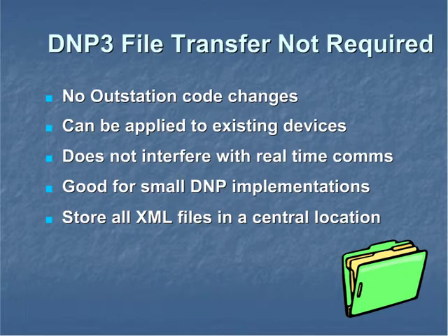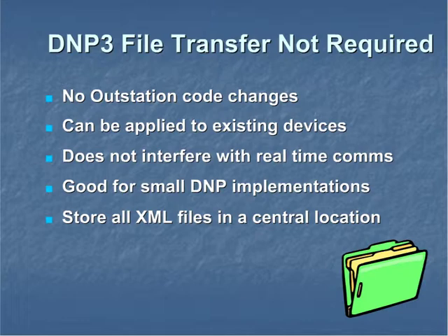Note that file transfer is not required for any subset level. Generally, all the XML files would be stored in a central network location. If DNP3 file transfer is supported, then it could be used to read current values from the device or write new configuration parameters to the device.